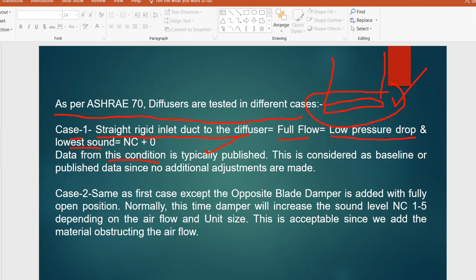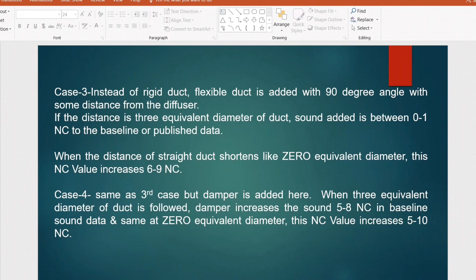In Case 2, the same arrangement is used but an opposite blade damper is added in the fully open condition. This increases the sound level by NC 1 to 5. So compared to the baseline NC value from the diffuser alone, adding the opposite blade damper causes an increment of 1 to 5 in the sound level.